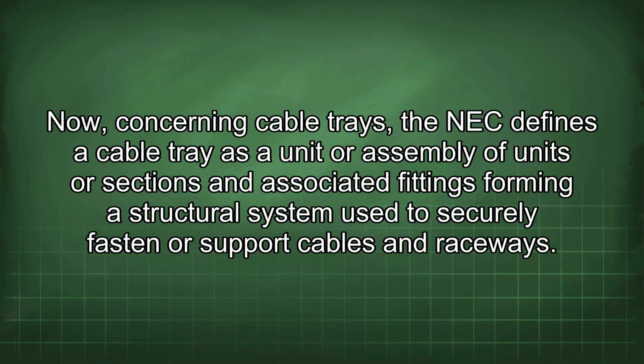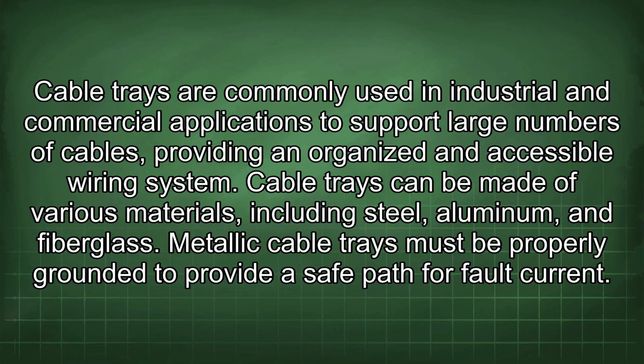Now, concerning cable trays, the NEC defines a cable tray as a unit or assembly of units or sections and associated fittings forming a structural system used to securely fasten or support cables and raceways. Cable trays are commonly used in industrial and commercial applications to support large numbers of cables, providing an organized and accessible wiring system. Cable trays can be made of various materials, including steel, aluminum, and fiberglass. Metallic cable trays must be properly grounded to provide a safe path for fault current.